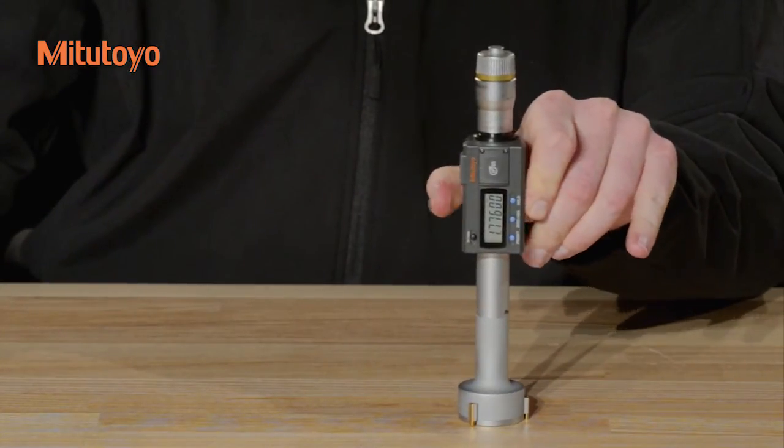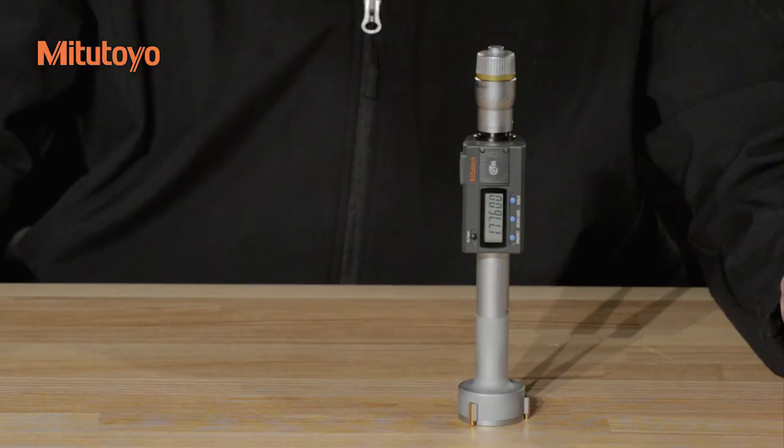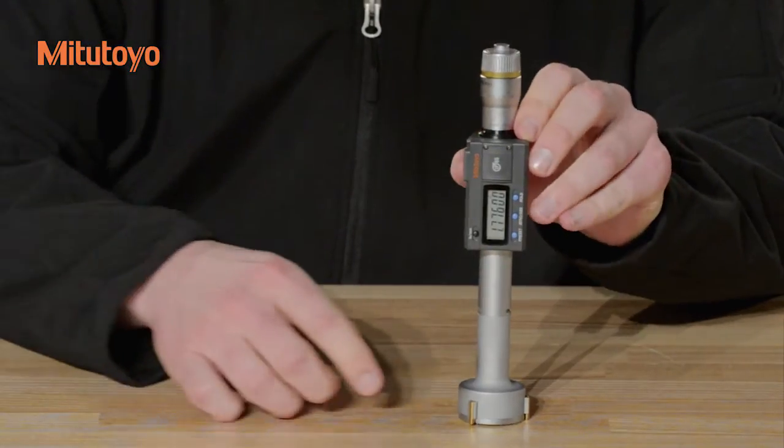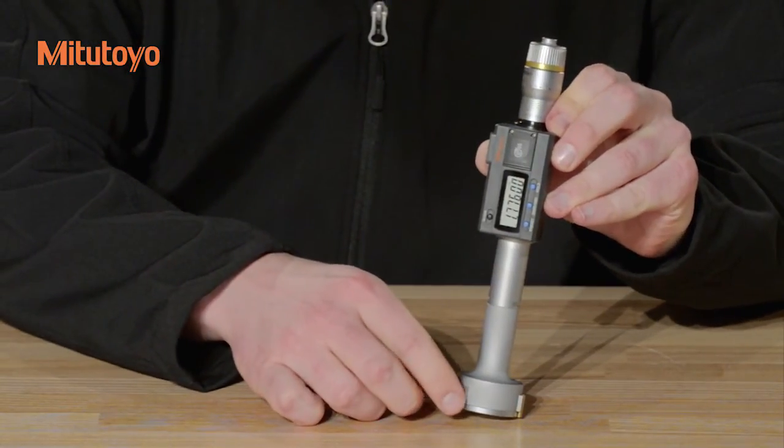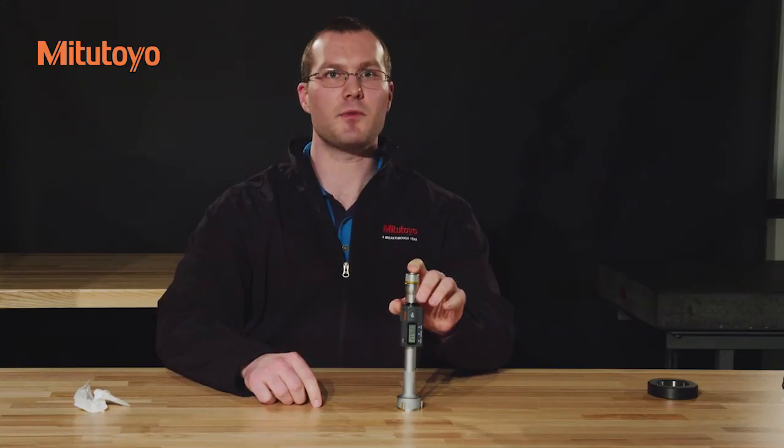Make sure you store the instrument in a room free from excessive heat, moisture, dust, and oil mist. And if storing the instrument for an extended period of time, apply micrometer oil to the anvils and contact surfaces. Lastly, remove the battery.